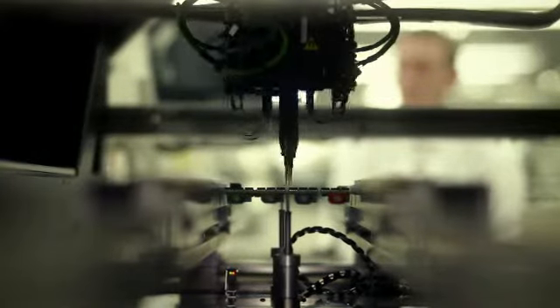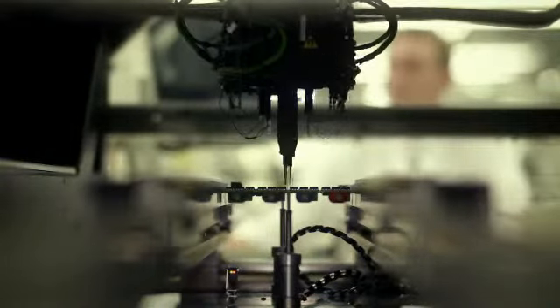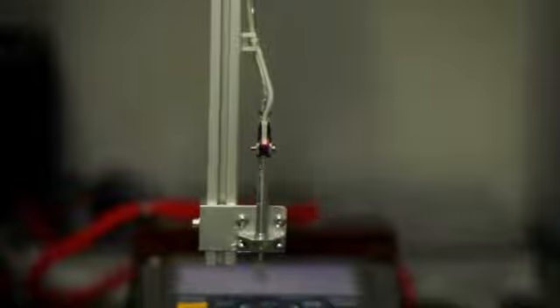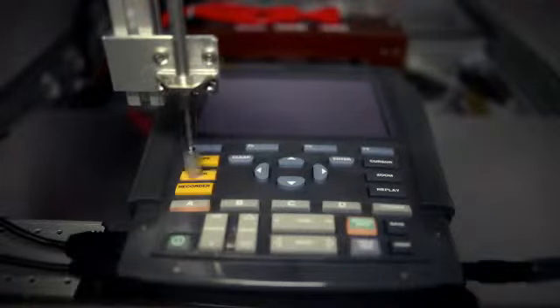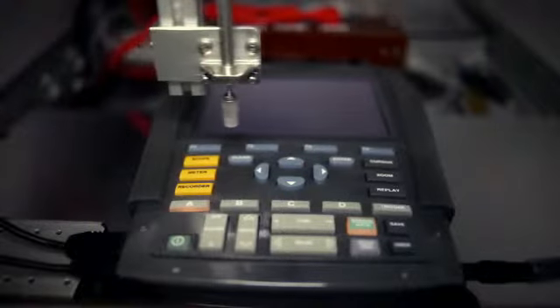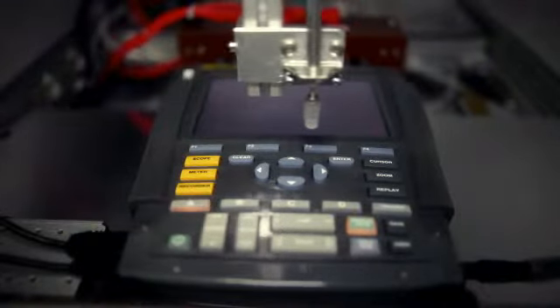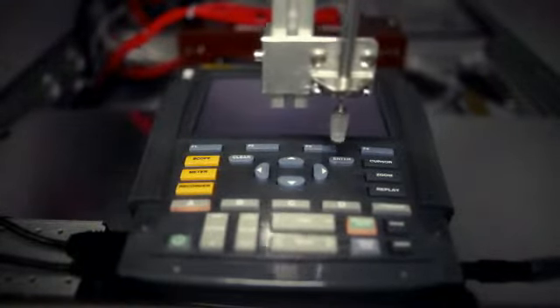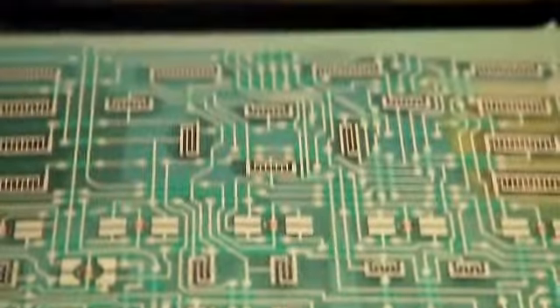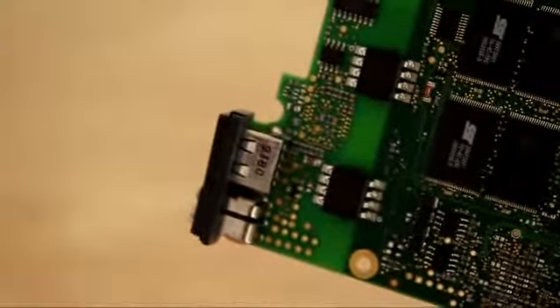During the implementation of the instrument's firmware, we set up a test that we run 24 hours a day, seven days a week. It's an automated test that presses the keys of the instrument. Pressing that key enters the bit of code and all the assertions are correctly passed. When an illegal condition is met, the instrument stops, mentions the line where the condition is a problem, and starts all over.